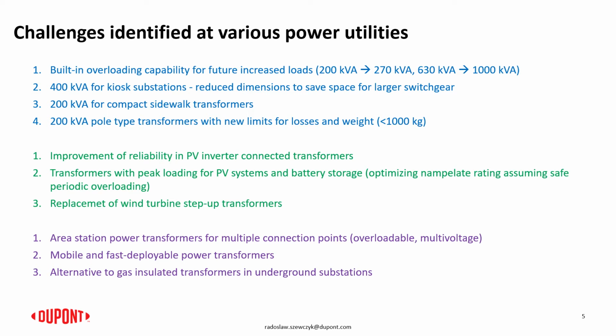providing versatility and interchangeability in the system, again to improve the possibility of moving the transformers from one location, or at least installing the transformers in multiple locations for limiting the number of spare transformers, or the possibility of quicker reaction to the situations in the network. We can also talk about the alternatives to the gas insulated transformers. For example, in underground substations, the solutions with alternative insulation systems can help in some installations here.